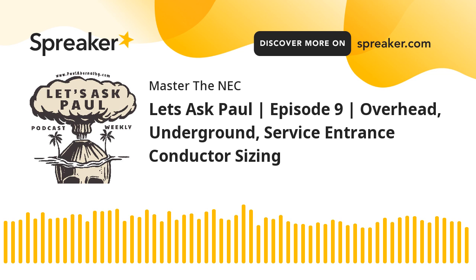Okay, so if you look at C, we're going to focus on C1 and C2 just because of where they send you as far as their reference. Because again, it told us that the grounded conductor cannot be smaller than what's given in 250.24(C). So it can't be less than the minimum size here. When you get here, you're going to notice real quickly in C1 and C2, it doesn't give you any sizes. Now, it does tell you in C2, when it comes to parallels, that it can't be smaller than 1/0. Okay, so that's a given, something you should remember, especially if you're preparing for an exam. You never have parallel conductors in general use that are paralleled smaller than a 1/0.